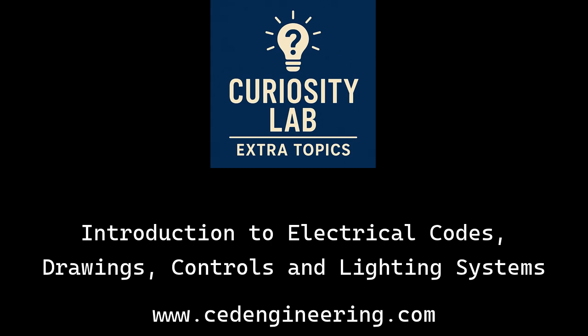Okay, rounding out this foundational part, grounding and bonding. We touched on the definitions, but Article 250, what's the big picture strategy there? Article 250 is arguably one of the absolute cornerstones of electrical safety. It sets out the rules for grounding and bonding, not as nice-to-haves, but as essential safeguards. The main goal is to create a continuous low-resistance path for electricity throughout the system's metal parts, and critically, a reliable path for fault current to flow back to the source. Why? So if something goes wrong, say a live wire touches a metal motor casing, that fault current surges back, trips the breaker or blows the fuse quickly, and de-energizes the circuit before someone can get shocked or a fire can start.